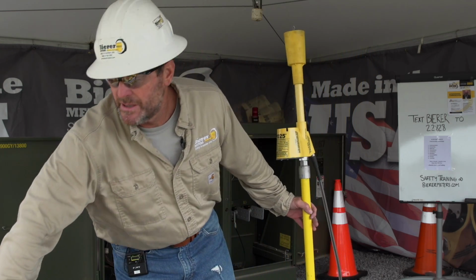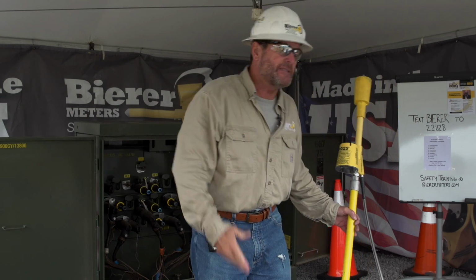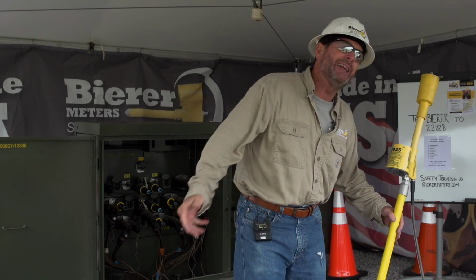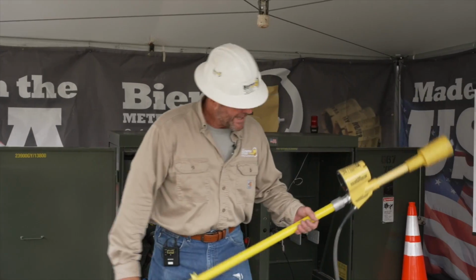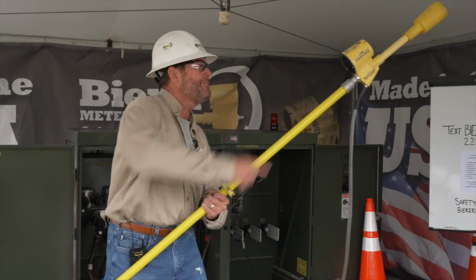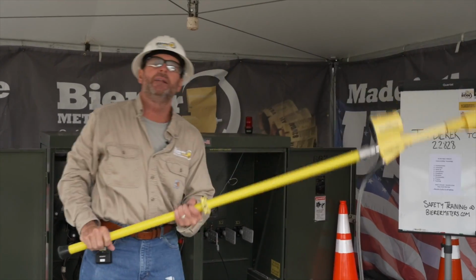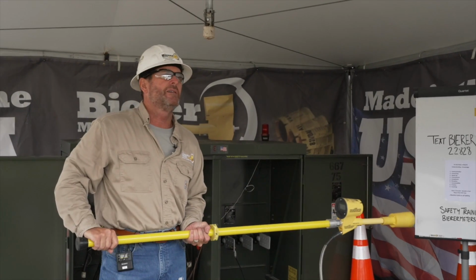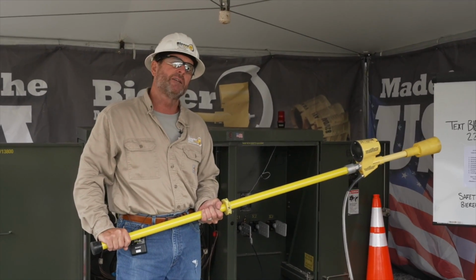But they didn't, because they needed the lineman safety and tool training, so they didn't know. So when they made contact, and that hot bus was right next to the meter head, they had a cross phase arc flash.